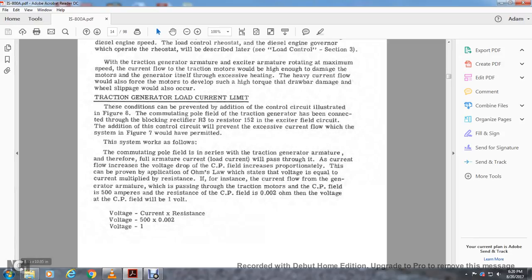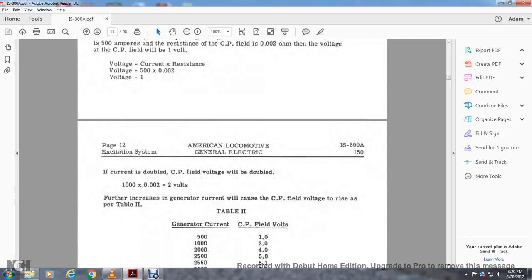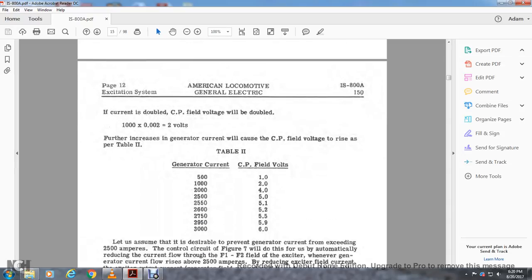Voltage equals current times resistance: 500 times 0.002 equals 1 volt. If current doubles, the CP field voltage doubles: 1000 amperes times 0.002 equals 2 volts. Further increases are shown in table 2: at 500 amperes, CP field volts = 1; at 1000 amperes = 2 volts; at 2000 amperes = 4 volts; at 2500 amperes = 5 volts; at 2550 = 5.1; at 2600 = 5.2; at 2750 = 5.5; at 2950 = 5.9; at 3000 = 6 volts CP field volts.